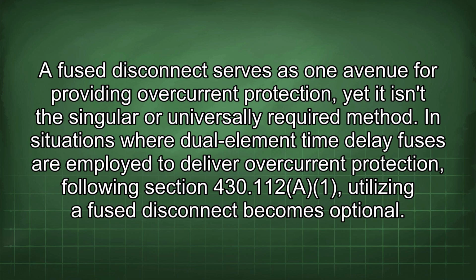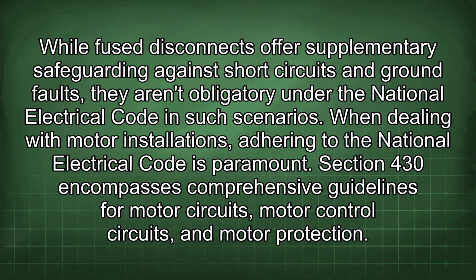In situations where dual-element time delay fuses are employed to deliver overcurrent protection following Section 430.112(A)(1), utilizing a fused disconnect becomes optional. While fused disconnects offer supplementary safeguarding against short circuits and ground faults, they aren't obligatory under the National Electrical Code in such scenarios. When dealing with motor installations, adhering to the National Electrical Code is paramount.